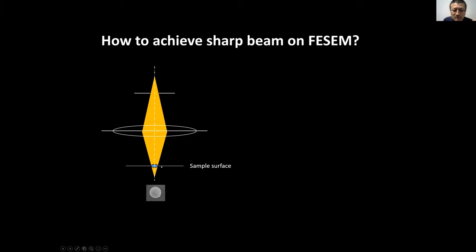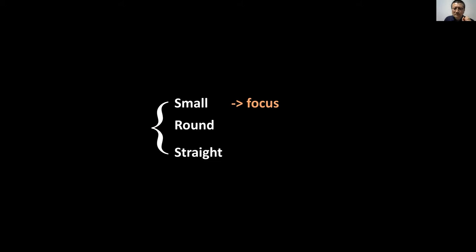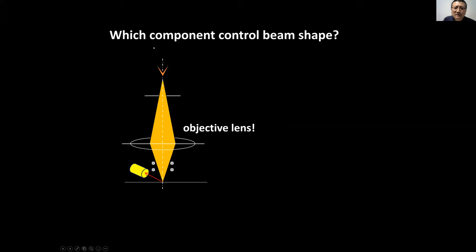When you change the working distance, you see the image become bigger and smaller, clearer and not clear. As a user, you always need to focus the beam first. When you make a good focus, you make the beam smaller. So what about the shape of the beam? Which component controls beam shape? Let's look at the lens — we use electromagnetic fields in the pole piece to focus the electron beam.